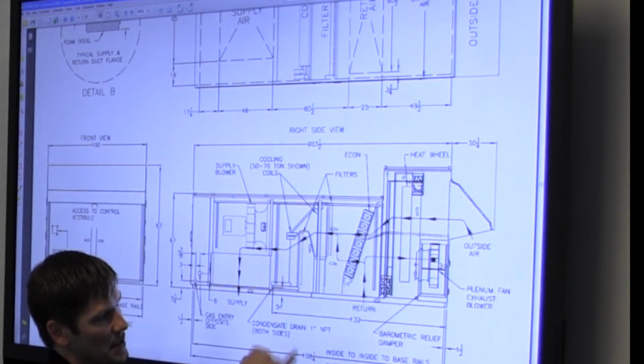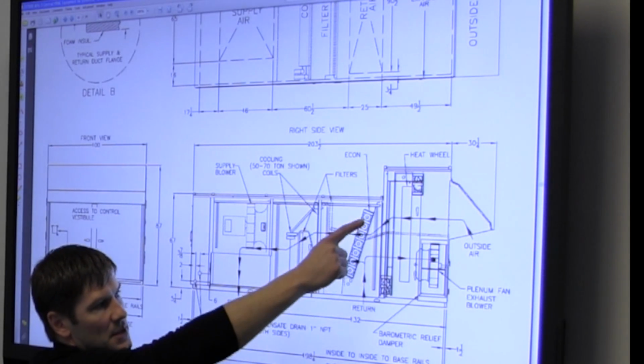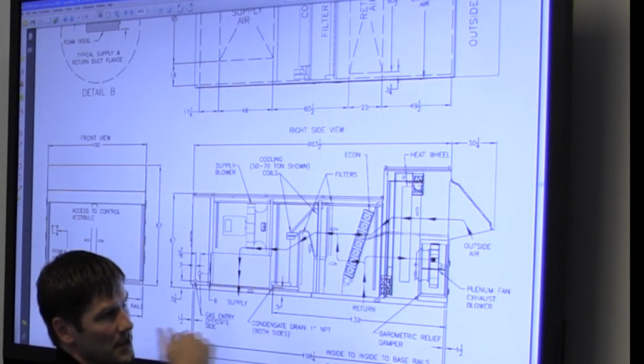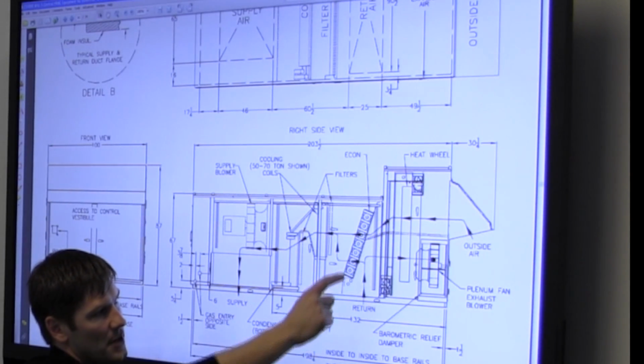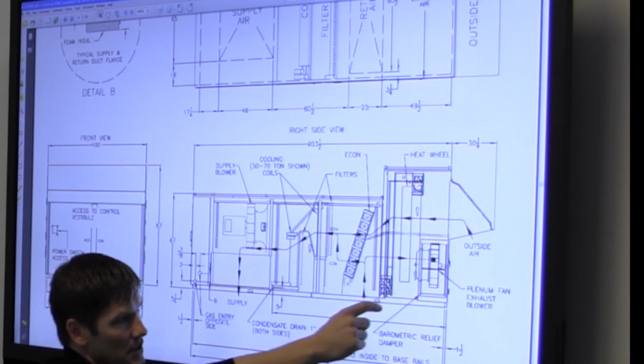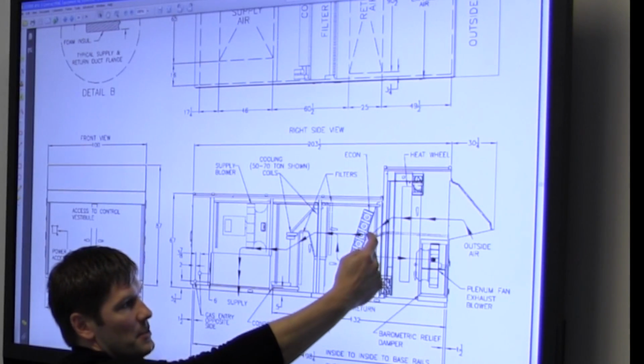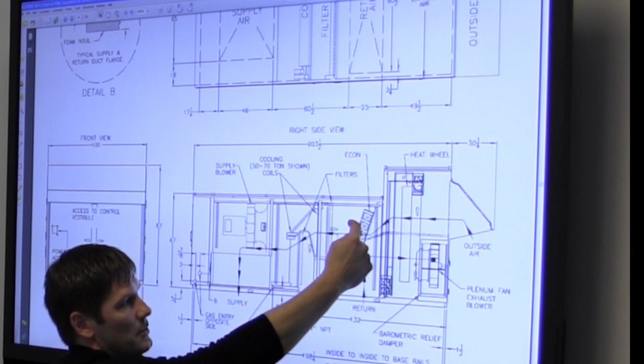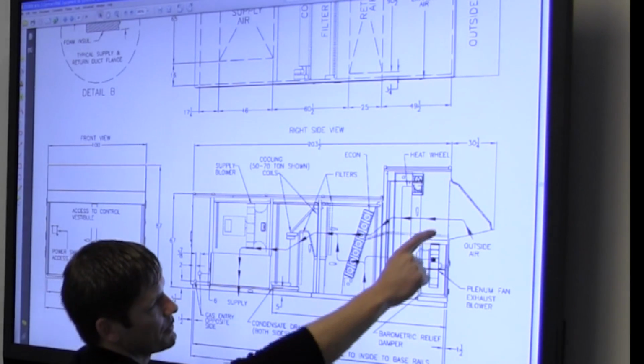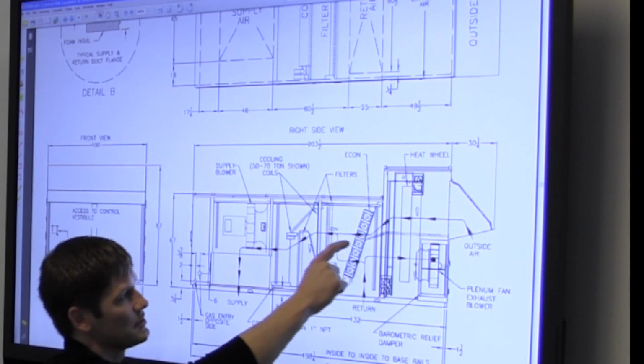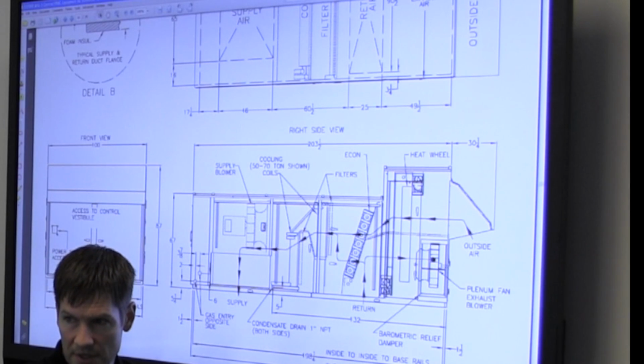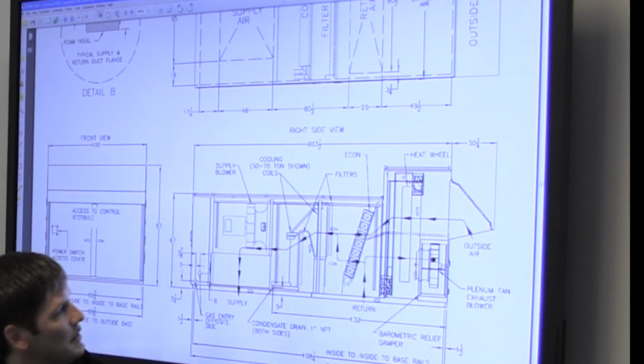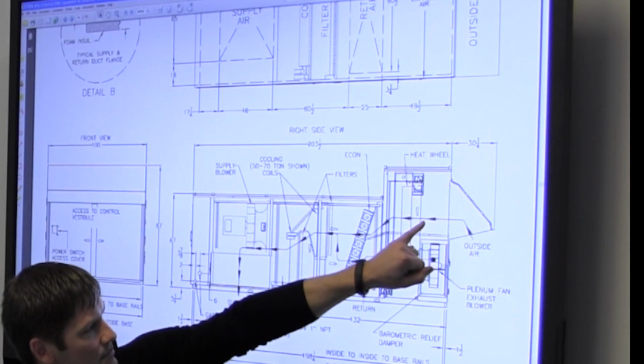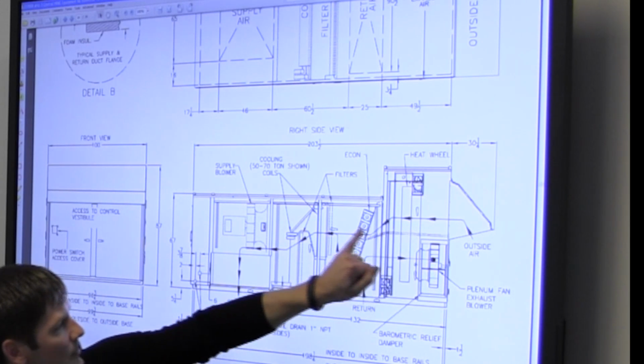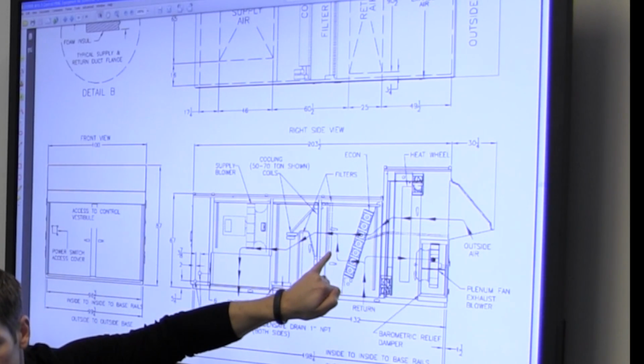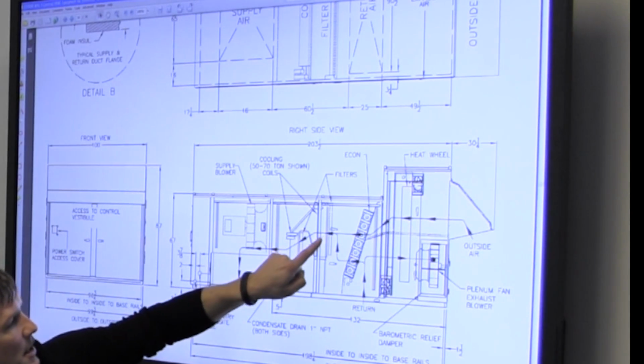These dampers are on gears, so if these are open, these are closed. If these are closed, these are open. For the most part, you'll always see these closed. The outside air is always going to come through here, gets heated up with the heat wheel, and there is a filter bank here, and there is a filter bank here. Those are the redundant filter banks I was talking about. Here it's a 2-inch 30% filter. Here there's a 2-inch 30% filter, filtering that exact same air.